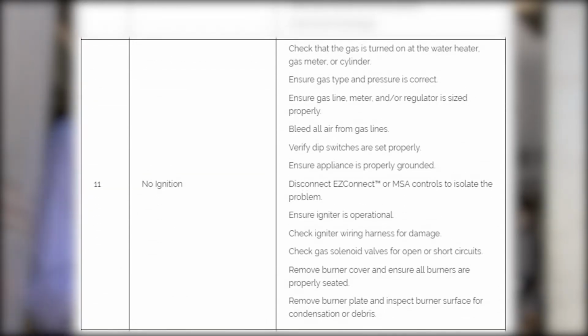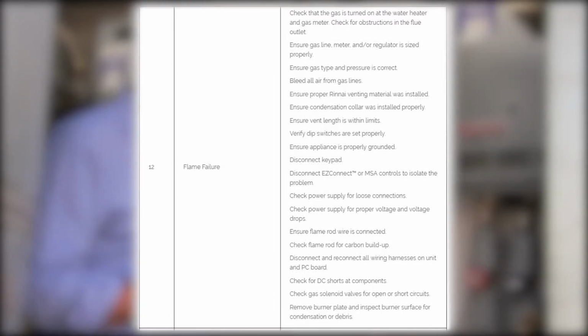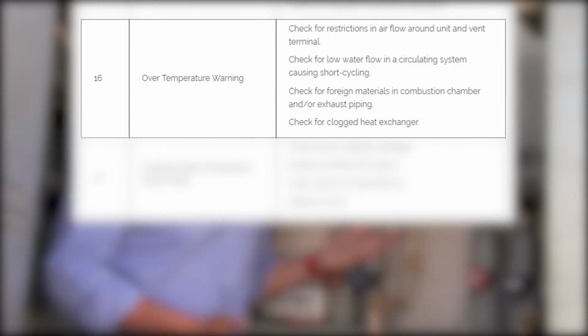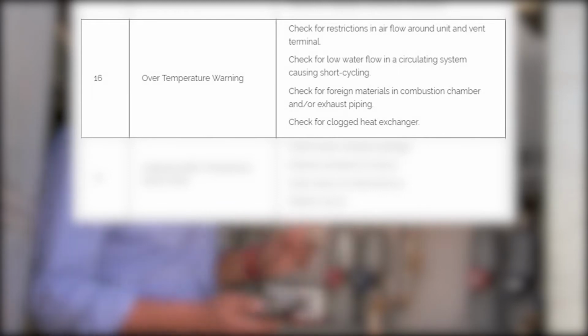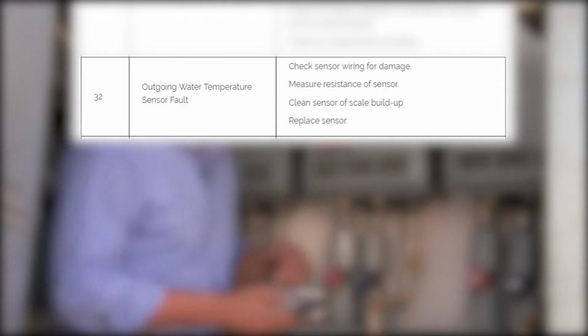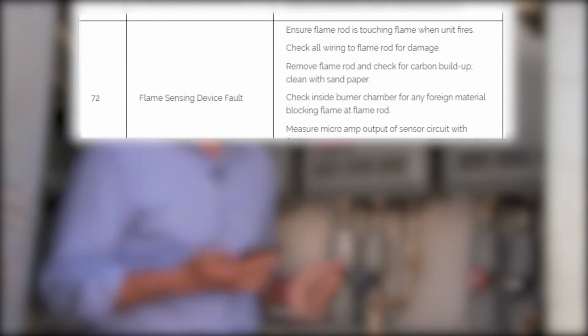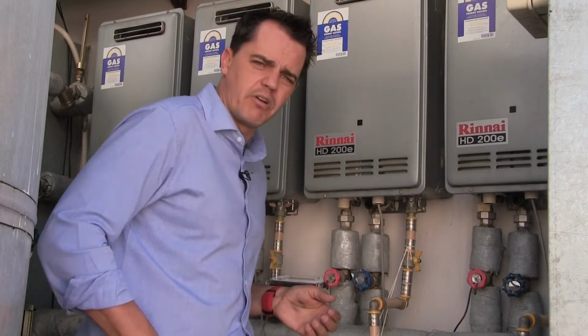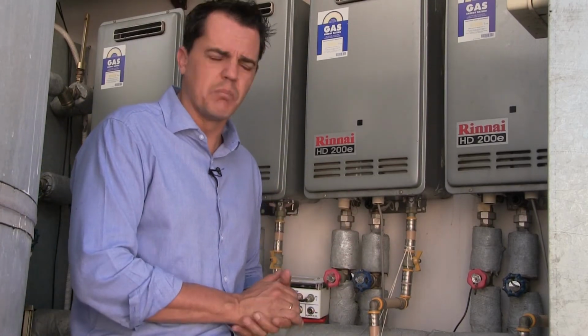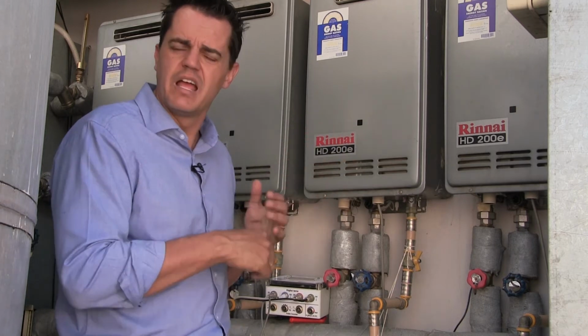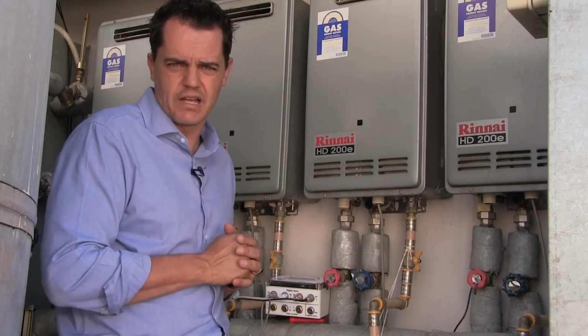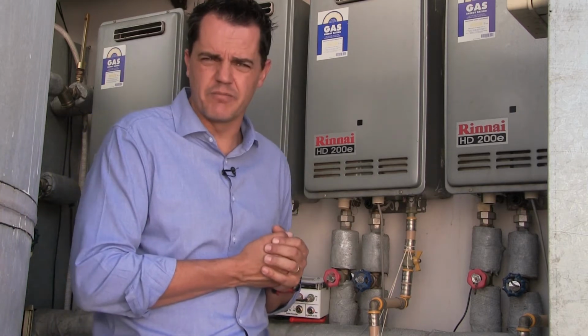Then we've got an error code 11, no ignition. Again, it's an internal problem. Error code 12, flame failure, internal problem. Error code 14, thermal fuse. Error code 16, over temperature warning. In other words, again, we've got a blockage in the circulation pipes. Error code 32, outgoing water temperature sensor fault. And so it goes on up to error code, in fact, 72, flame sensing default unit. So when you've identified the error codes, we at least know what's wrong. But the point is, if there's an error code, you have to get the Rinnai installers out to come and fix this, hence why we've got the preventative maintenance schedule.